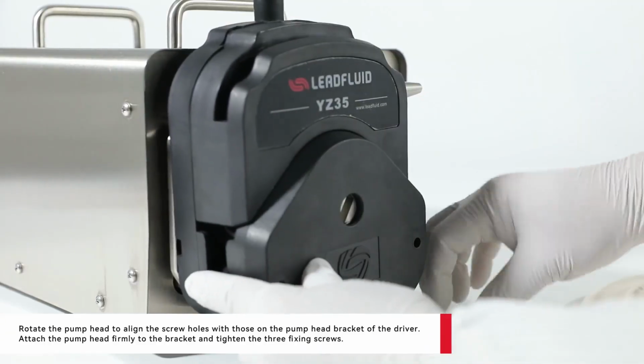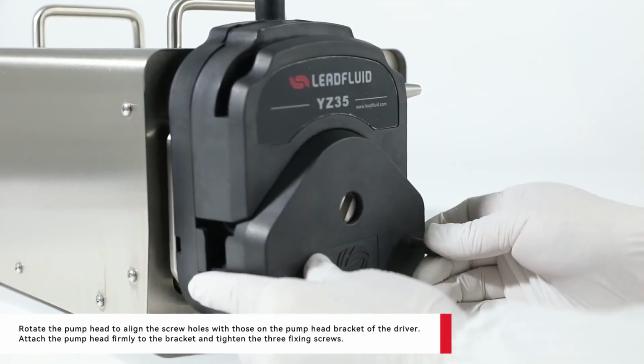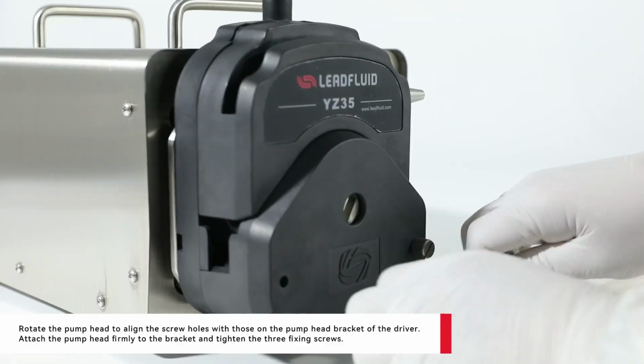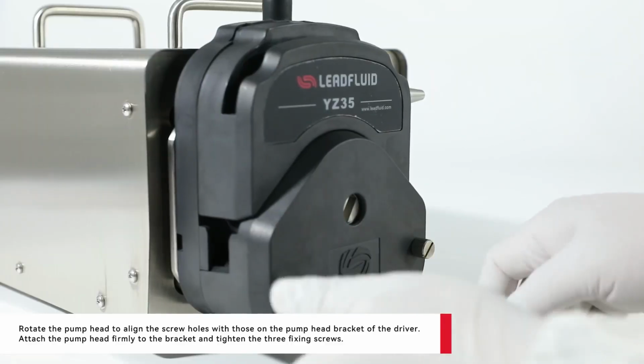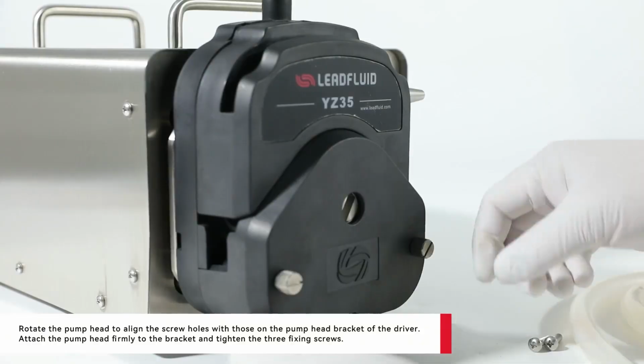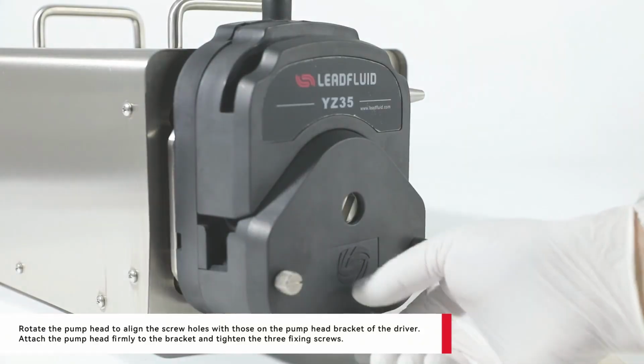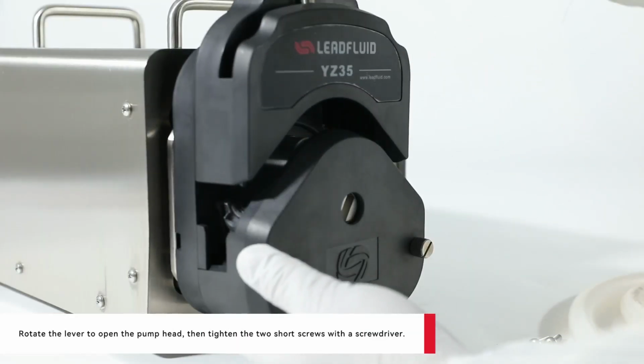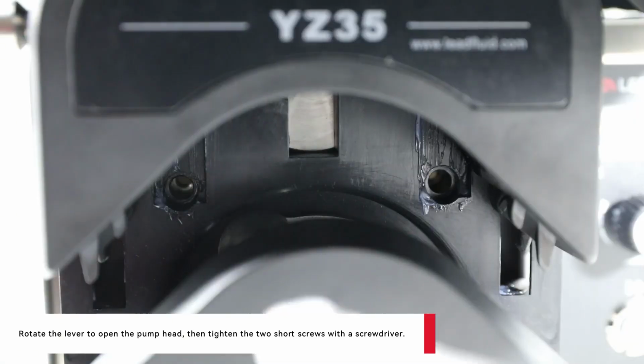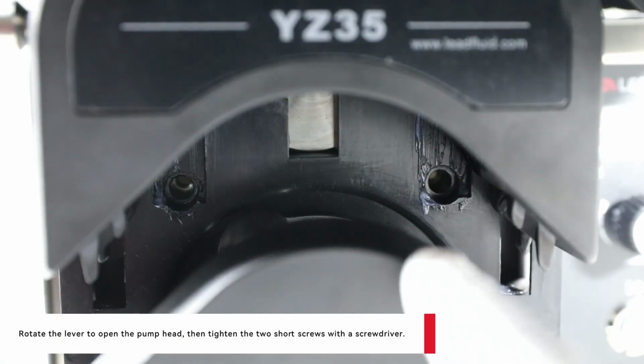Rotate the pump head to align the screw holes with those on the pump head bracket of the driver. Attach the pump head firmly to the bracket and tighten the 3 fixing screws. Rotate the lever to open the pump head, then tighten the 2 short screws with a screwdriver.